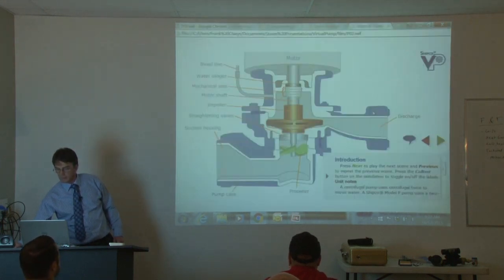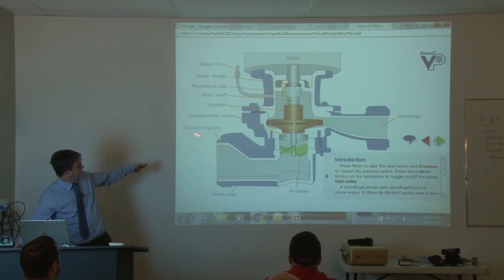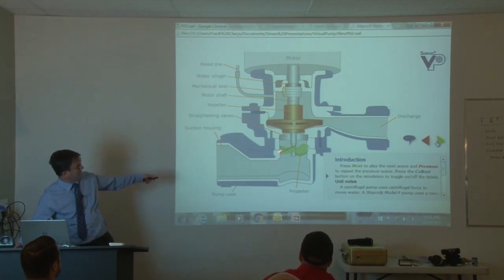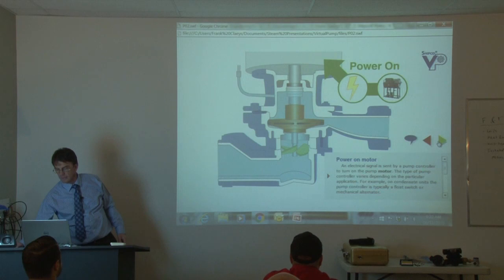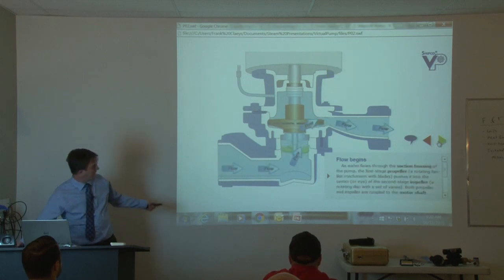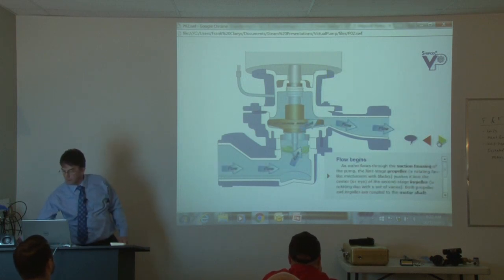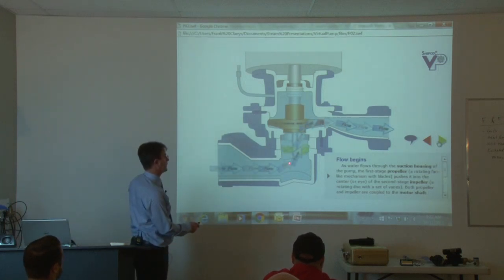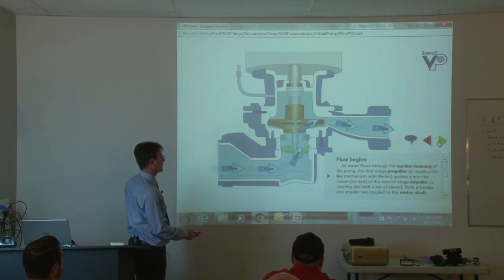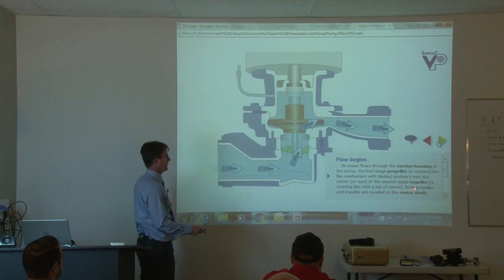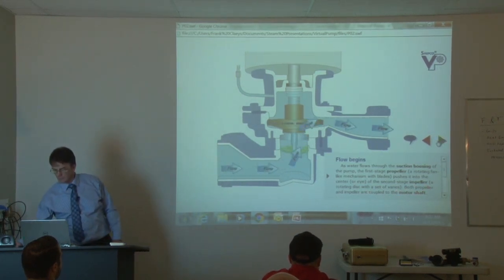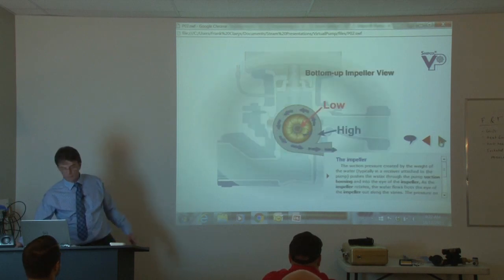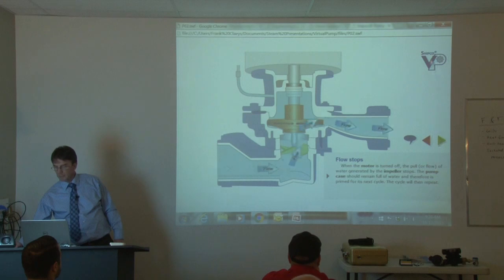The Model P is the same as the D except for the added propeller. Air gets exhausted the same way. When power turns on, the little propeller begins to spin. As water flows through the suction housing, the first-stage propeller - a rotating fan-like mechanism with blades - pushes water into the center of the eye. The second-stage impeller - a rotating disc with vanes - pushes the water out of the chamber. Same operation as the Model D; be careful of cavitation.